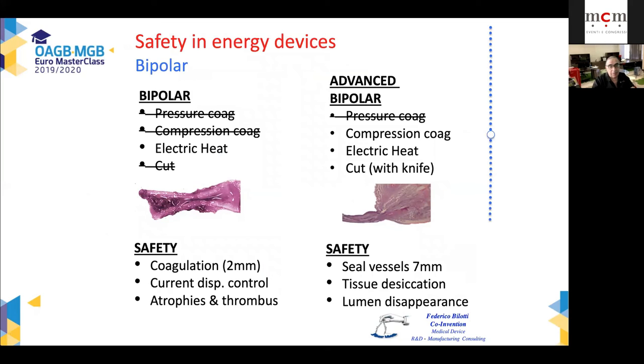Interesting what happened between bipolar and advanced bipolar. Normal bipolar is used often, but doesn't have compression. The heat is the only aspect that provides damage to the tissue and reaches the wanted coagulation. The advanced bipolar has compression. That's the main difference. And because of the compression, it can reach higher temperatures, can remove the water from the tissue, and can reach coagulation faster.